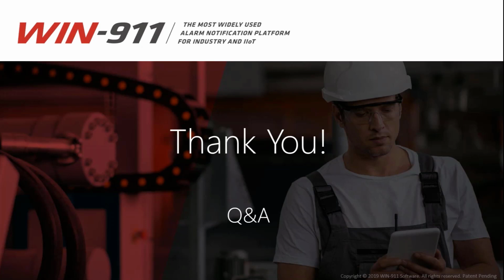Next question, does WIN-911 always look at the schedule for a connection first? For example, delays wouldn't apply if a connection wasn't currently on call. The delays are always evaluated. So if I kind of get where you're going with that. It's like if you had person 1 and then person 2 and person 3 in your call out list, and you had a delay between person 1 and person 2, but neither of them were on schedule, so person 1's off schedule, person 2's off schedule, but person 3 is on schedule, then those delays will be honored. I'll have to double check with that.